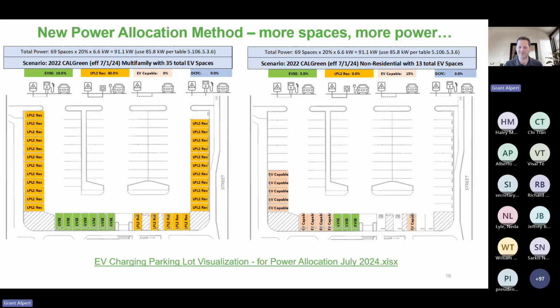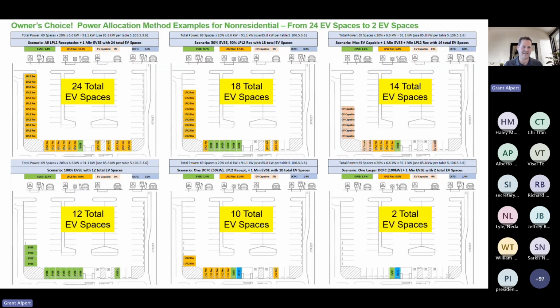So the power allocation gives you so much flexibility. And here's another example. You can have this 24 total EV spaces, you can have 18, 14, 12, 10, and just 2. So all of these meet the code, but they're just different allocations of receptacles versus EV installed versus DC fast chargers. So in the bottom middle and bottom right, there's a DC fast charger that takes up a lot of the power allocated, and there's just that one level 2 charger that's required.